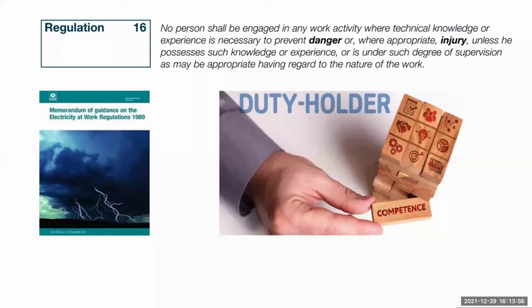Your employer could argue that you don't need a safe isolation kit because they are in charge of the installation. And while that may be true, they still have obligations under the Electricity at Work regulations and still need to perform safe isolation for any circuit that is being worked on. I would argue even more so for persons under their supervision, as they are the duty holder, and it would not look favourably in court if they failed in that duty.